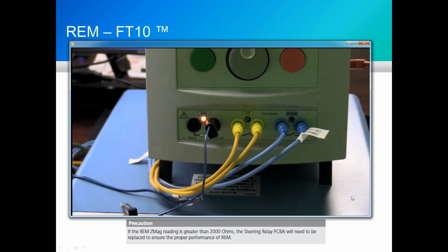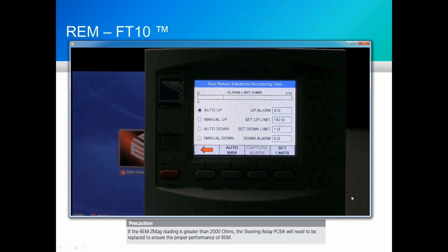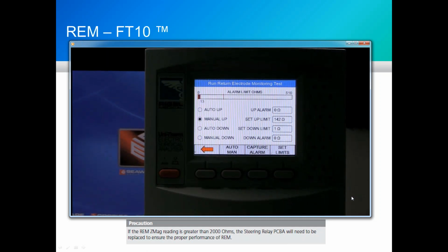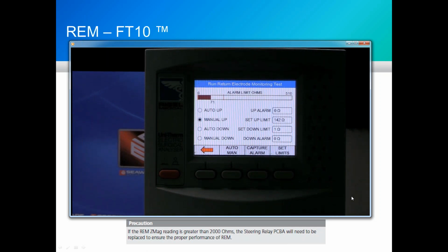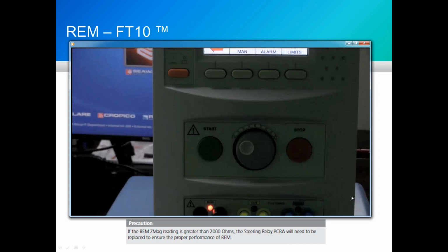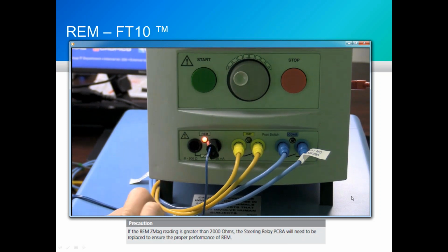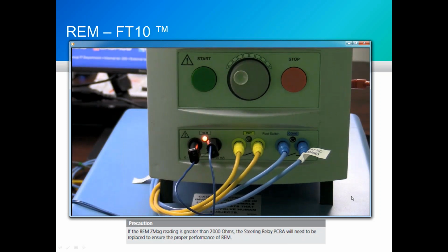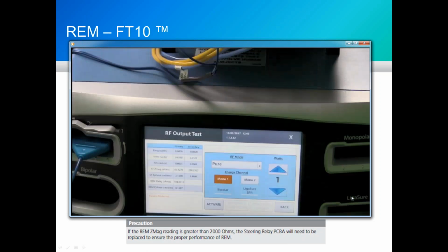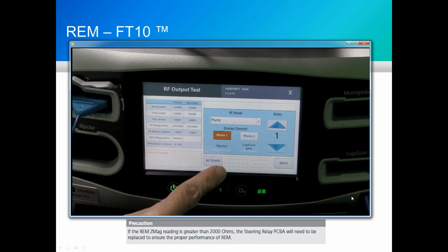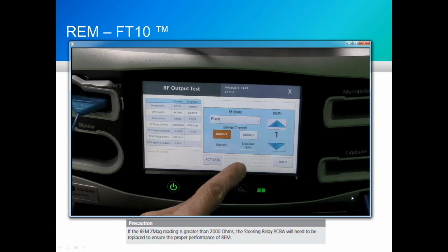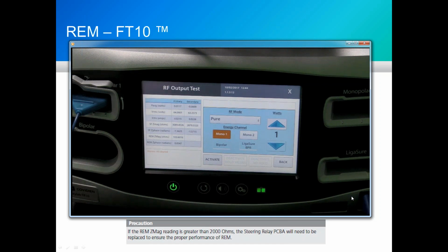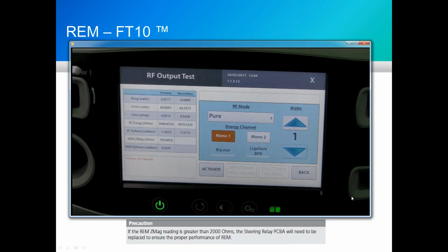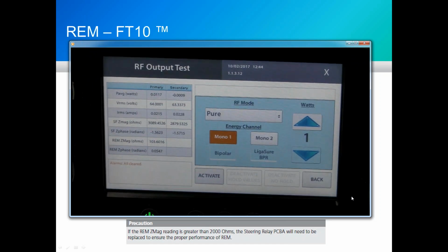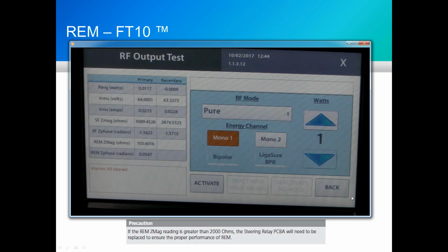I'm going up now and I'm going to make the second connection to our REM test circuit. But before I do that, I'm going to set the resistance value for 100 ohms. Make the final connection. And down where it says REM ZMAG on the screen, you'll see that we measure 103.6 ohms, which is within the acceptable range of what we're looking for.